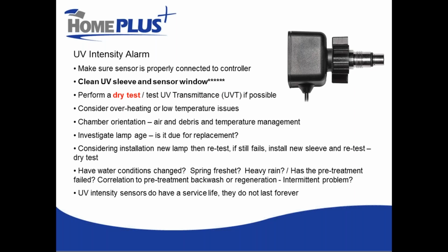Or if you're lucky enough to have a UV transmittance testing machine, and I know not everybody does, but if you do, you can do a UV transmittance test on your water, and again, capture the water, ideally that is literally in the chamber at the moment you're having an alarm, or at a sample port right beside it. If your UV transmittance is low, especially below 75%, that's probably the cause of your alarm. The problem is not your UV sterilizer. In fact, your UV sterilizer is doing exactly what it's supposed to do and warning you that it can't treat this water adequately anymore because your pre-treatment is either failing or inadequate.